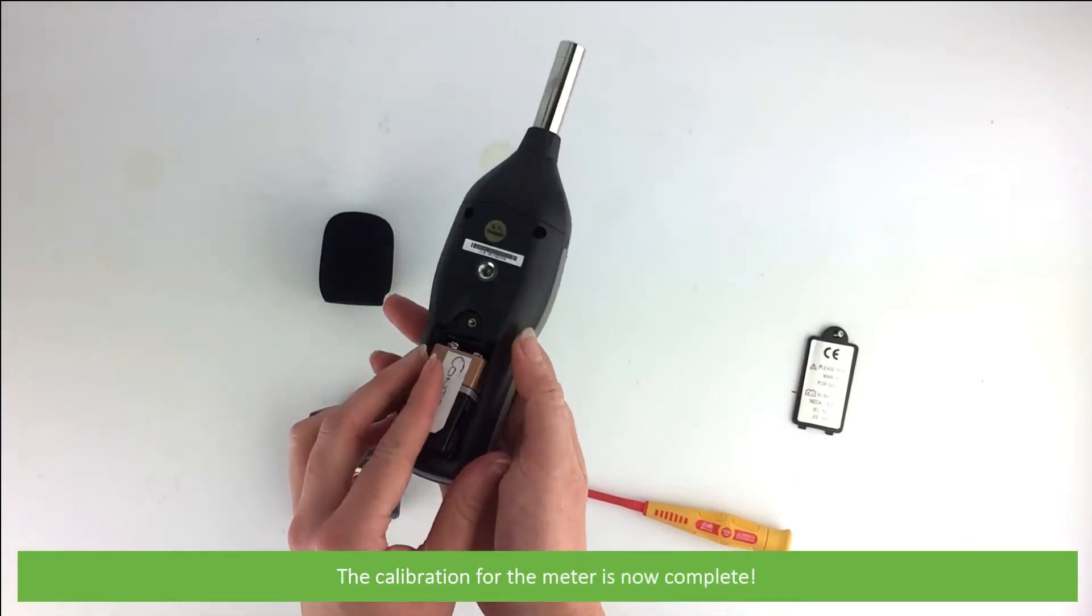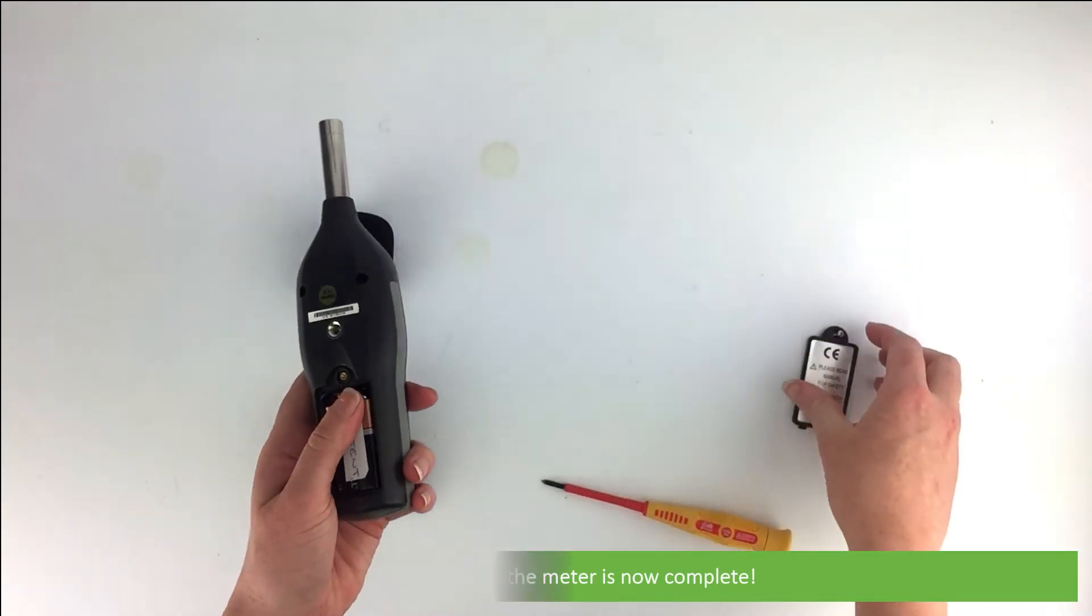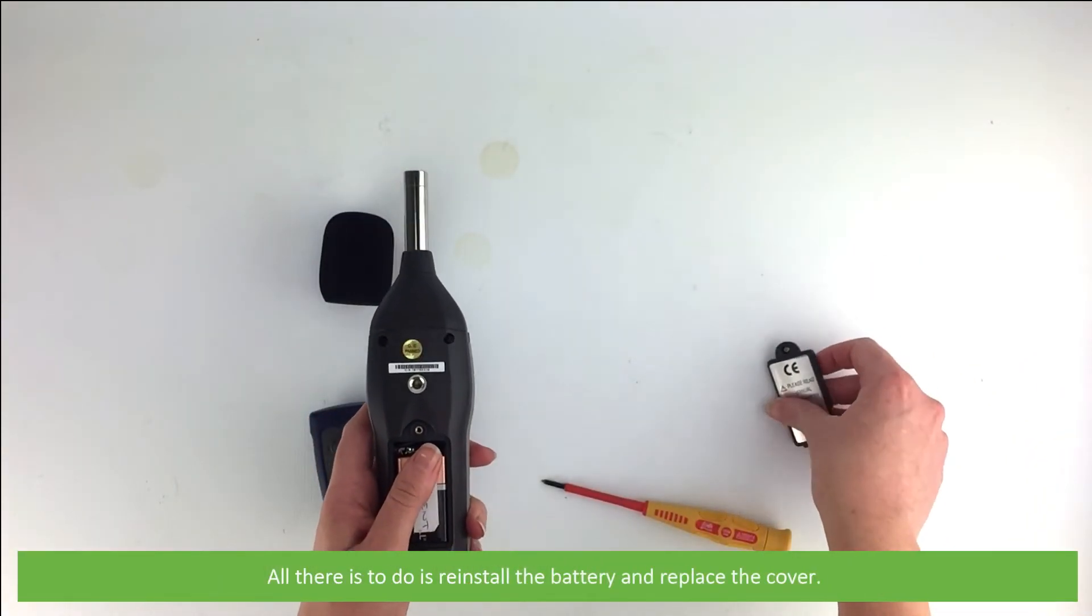The calibration for the meter is now complete. All there is to do is reinstall the battery and replace the cover.